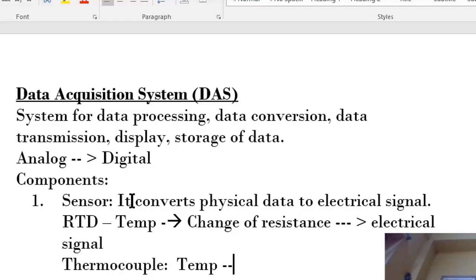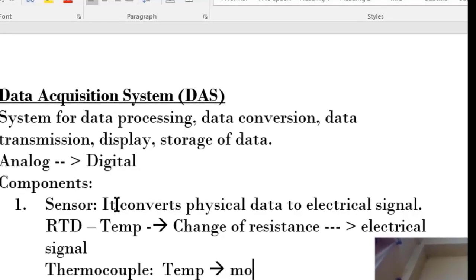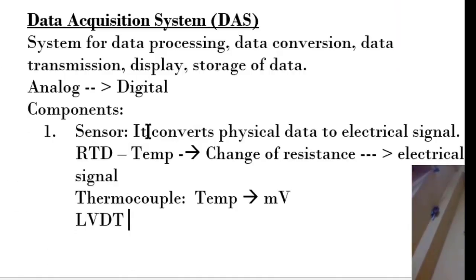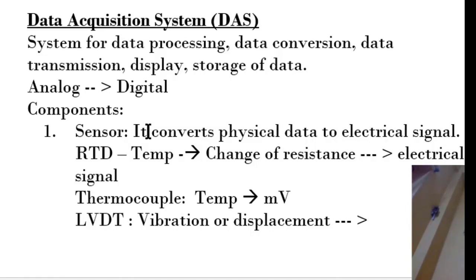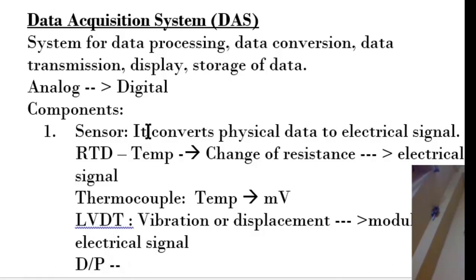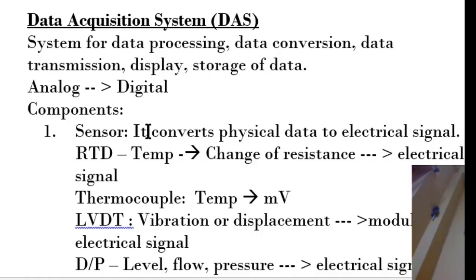A thermocouple senses temperature and gives an output in millivolts. LVDT, the linear variable differential transducer, measures vibration or displacement and gives a modulated electrical signal. A DP transmitter basically measures level, flow, or pressure and ultimately gives an electrical signal.